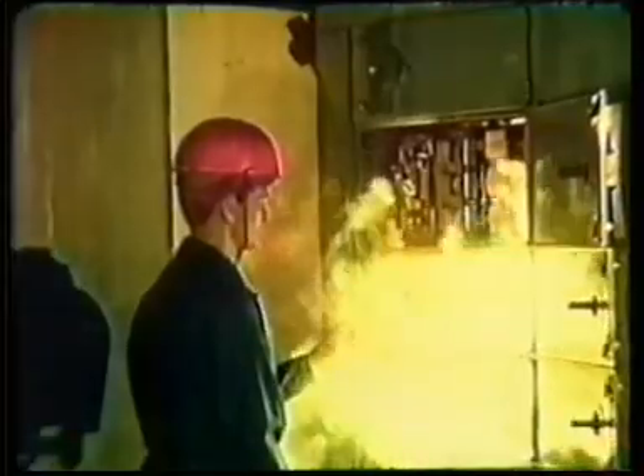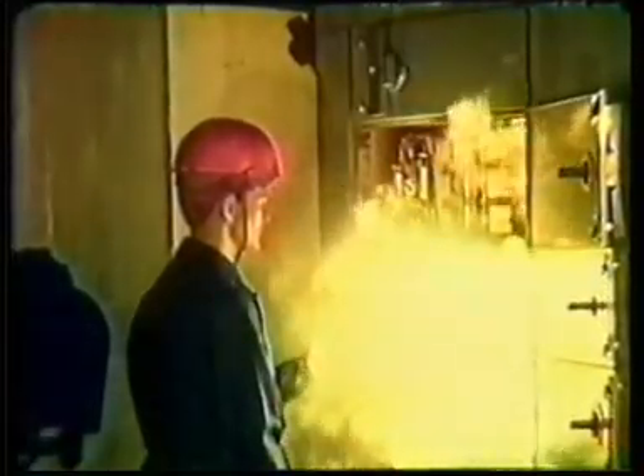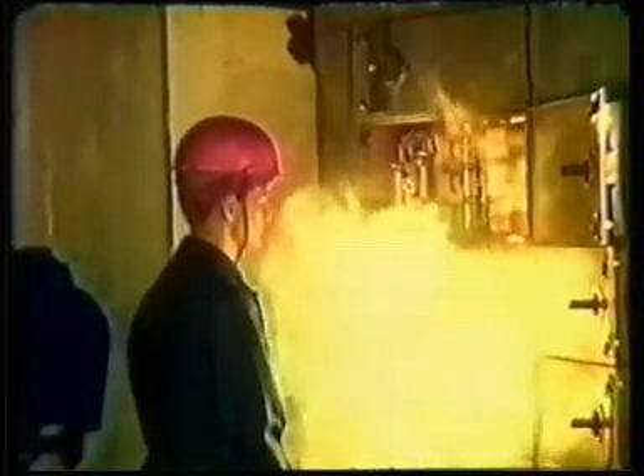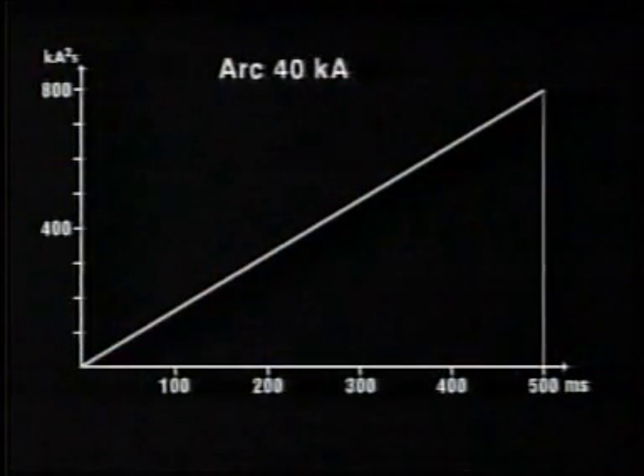An arc rapidly gives rise to a very powerful increase in pressure. At 10 kV and a short-circuit current of 40 kA, the pressure in the vicinity of the arc rises to about 15 tons per square meter within 10 milliseconds. The temperature of the arc increases violently to 20,000 degrees and causes a heat blast. Simply expressed, the energy released from the arc is equal to the square of the current times the duration.